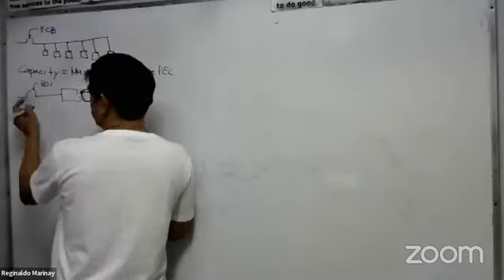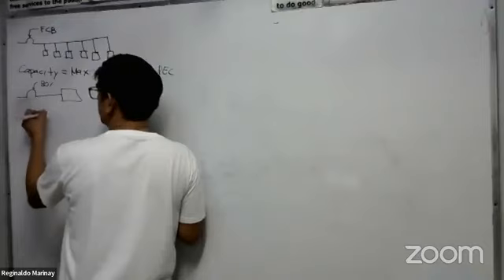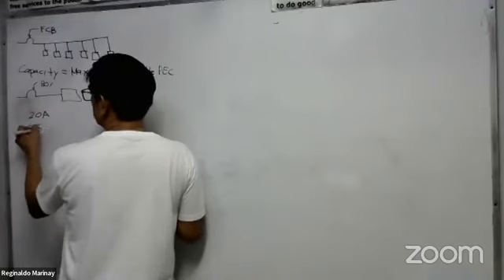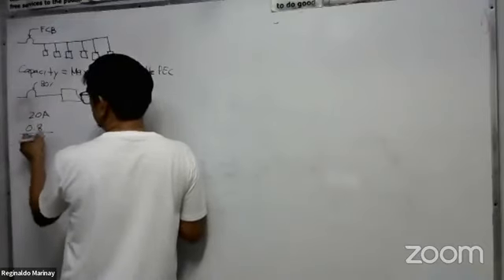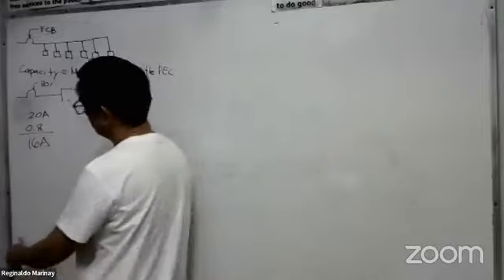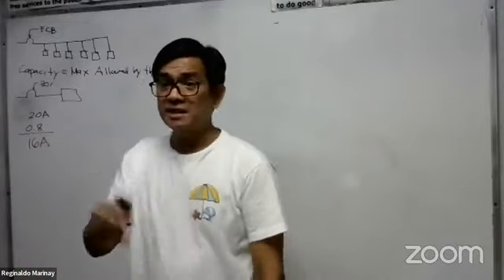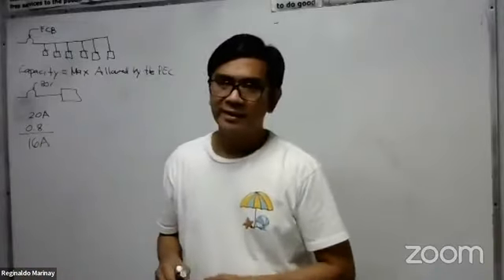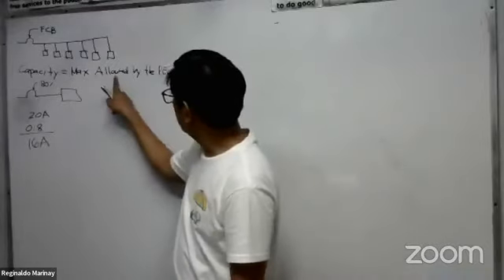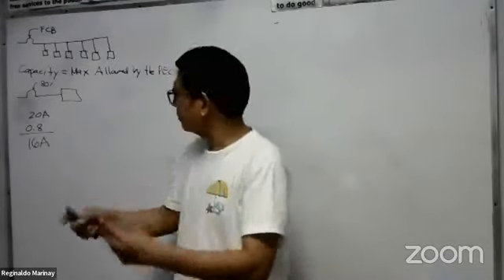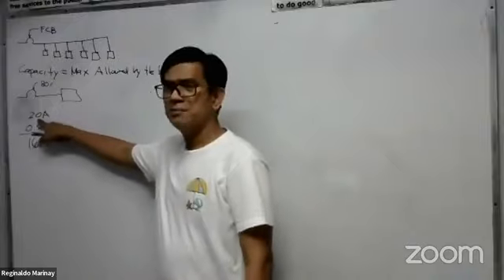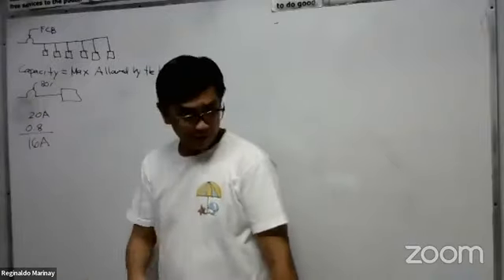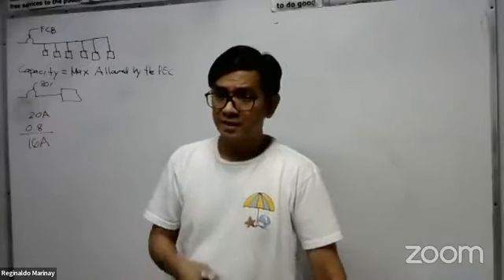Okay? For example, we have a circuit breaker of 20 ampere. So we have 0.8, so we have here 16 amps. That will be your capacity. That is the maximum allowed by the PEC. Although, of course, a 20 ampere breaker can carry up to 20. Yes, of course.